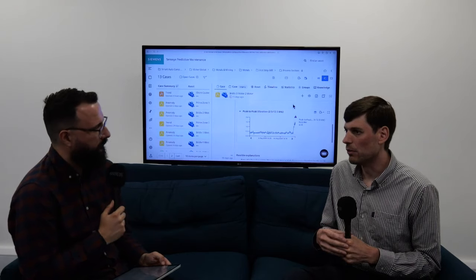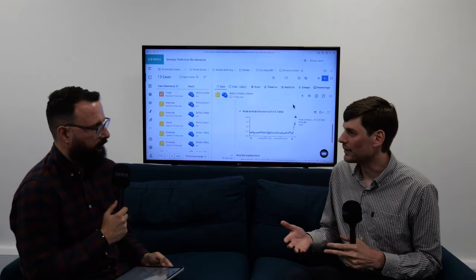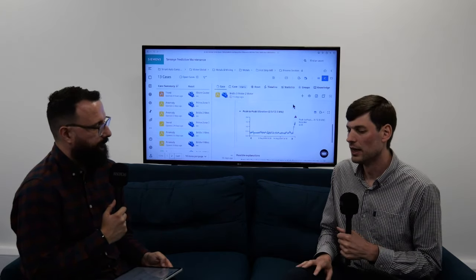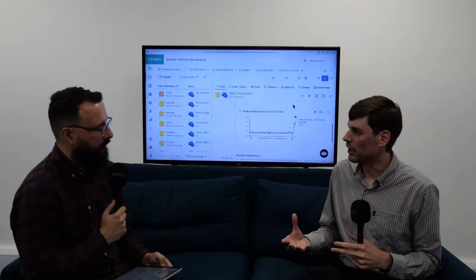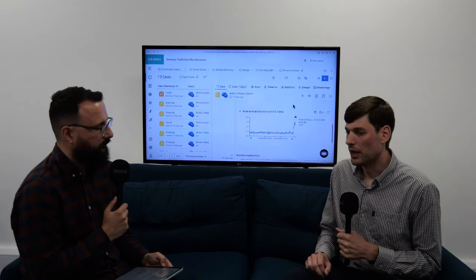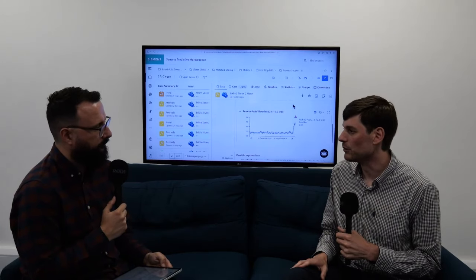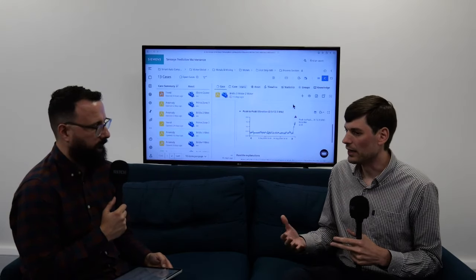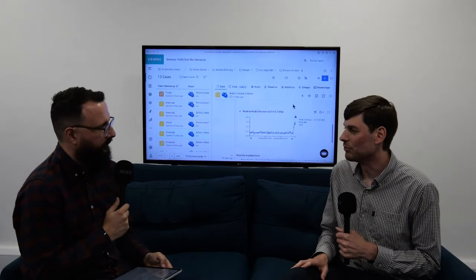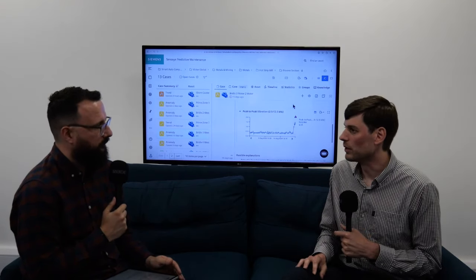We were monitoring oil levels on a hydraulic system in a steel mill, and through our normal analysis, we identified that the oil levels were dropping, and we forecasted that it would cause problems if that continued. So a case was raised, and as part of the prescriptive guidance, the top possible cause that was raised was a leak. And when our customer inspected the system, they found a broken weld in the piping where it was leaking. Through finding that quickly and fixing it, they were able to avoid 24 hours of downtime, which is really significant. So it's been really well received, and it's that additional level of guidance that people are benefiting from.